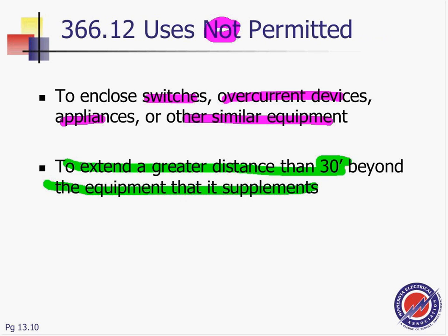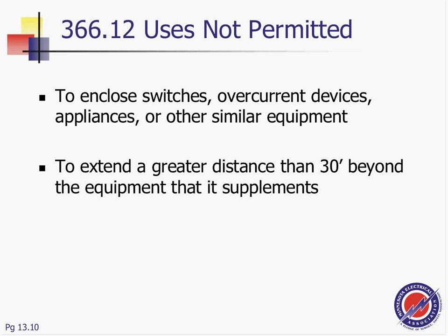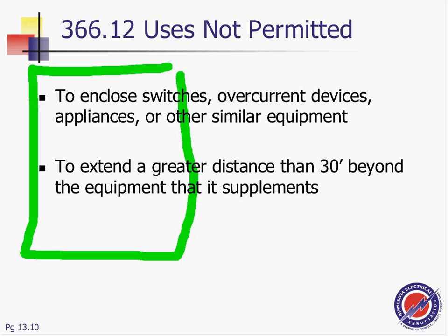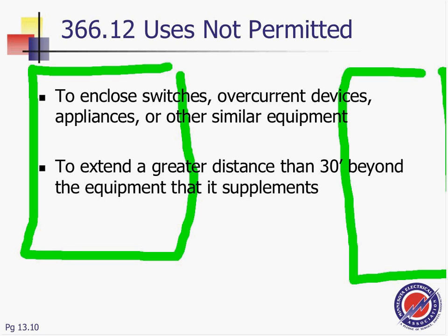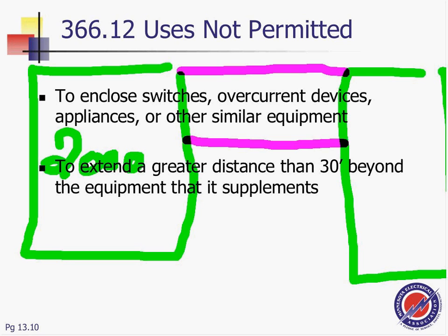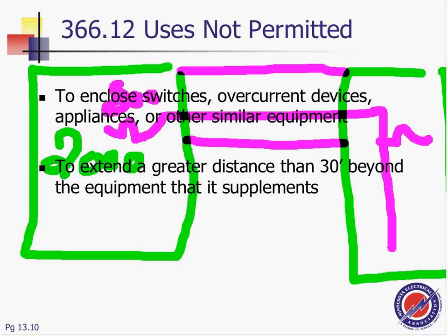So, good application, guys. We use them all the time. This is equipment, an existing piece of equipment. This is a 2,000 amp switchgear. You put a gutter right in between here, and you take a feeder from this one. See, I want an 800 amp feeder and a 100 amp panel here. Like that. And you can pull your conductors and extend it.